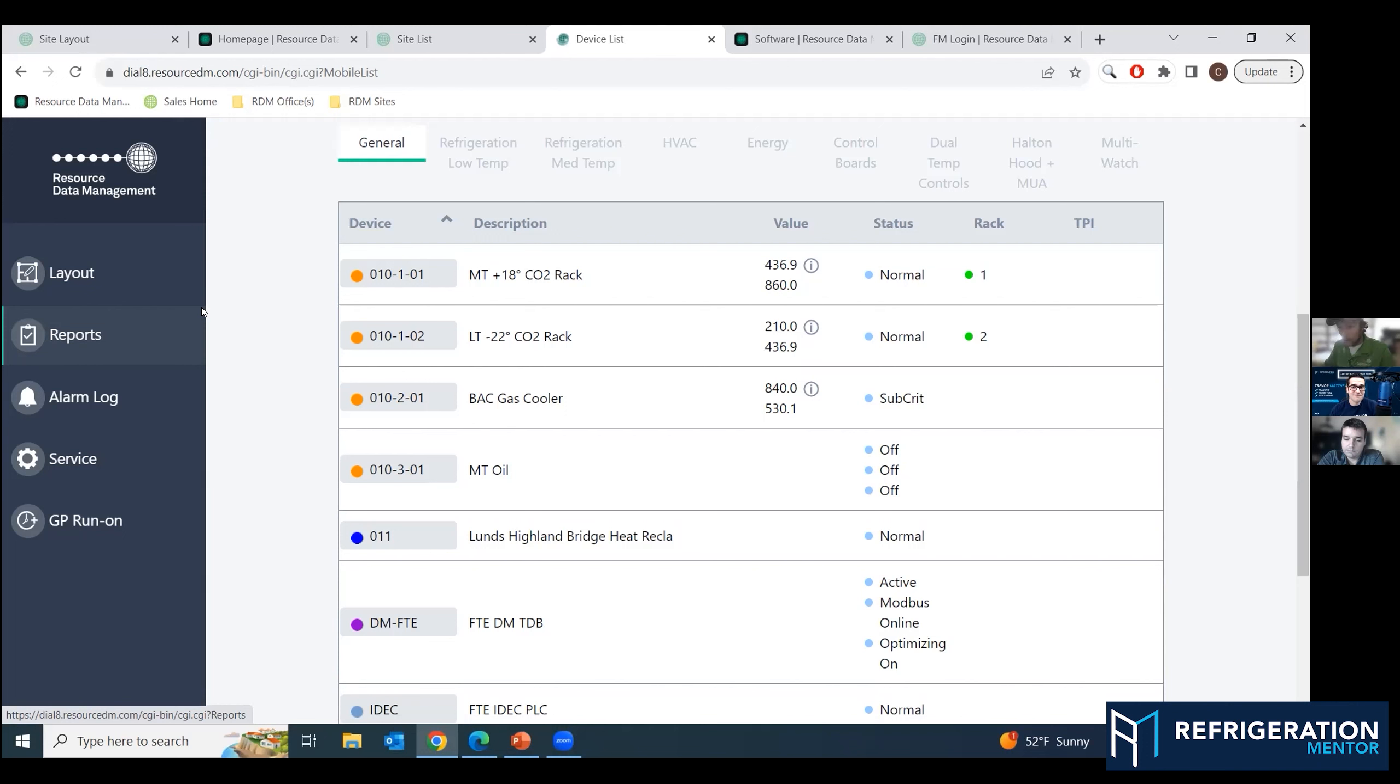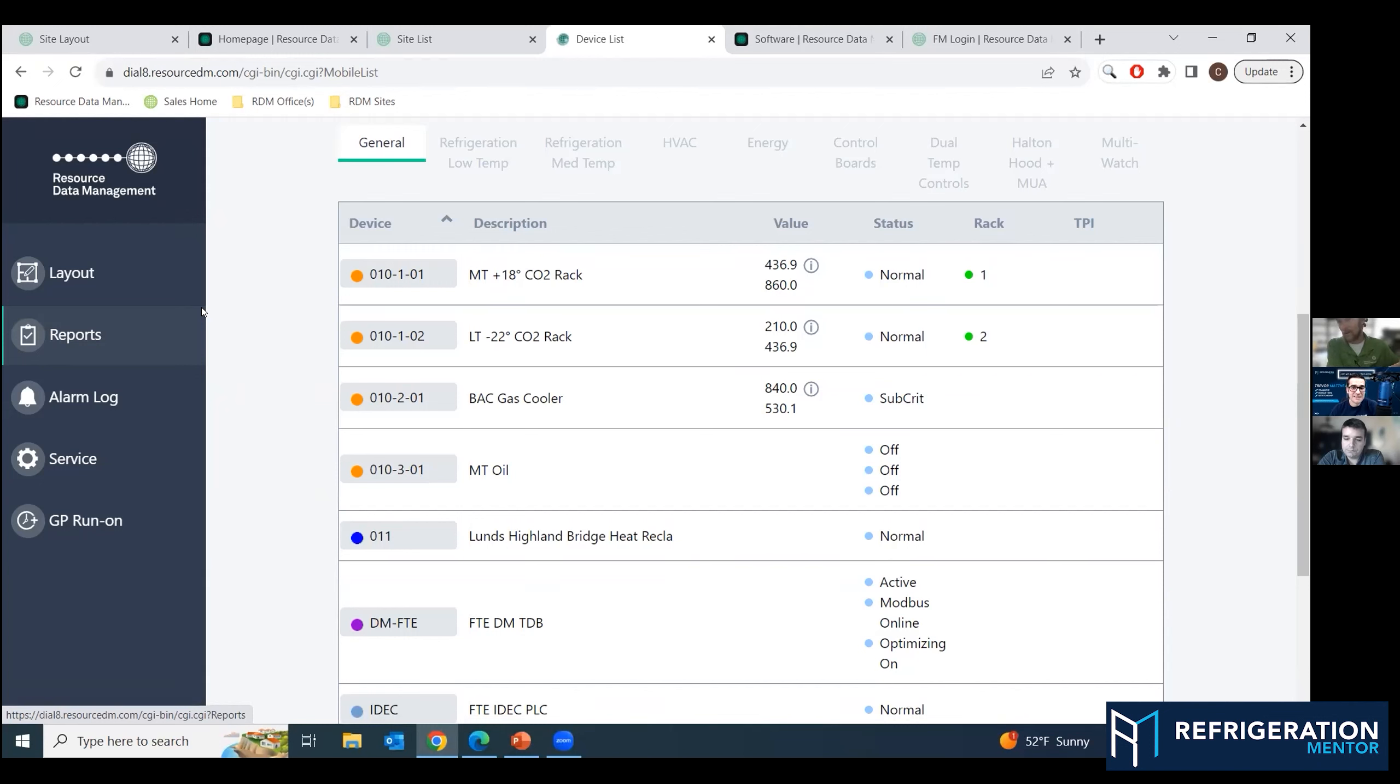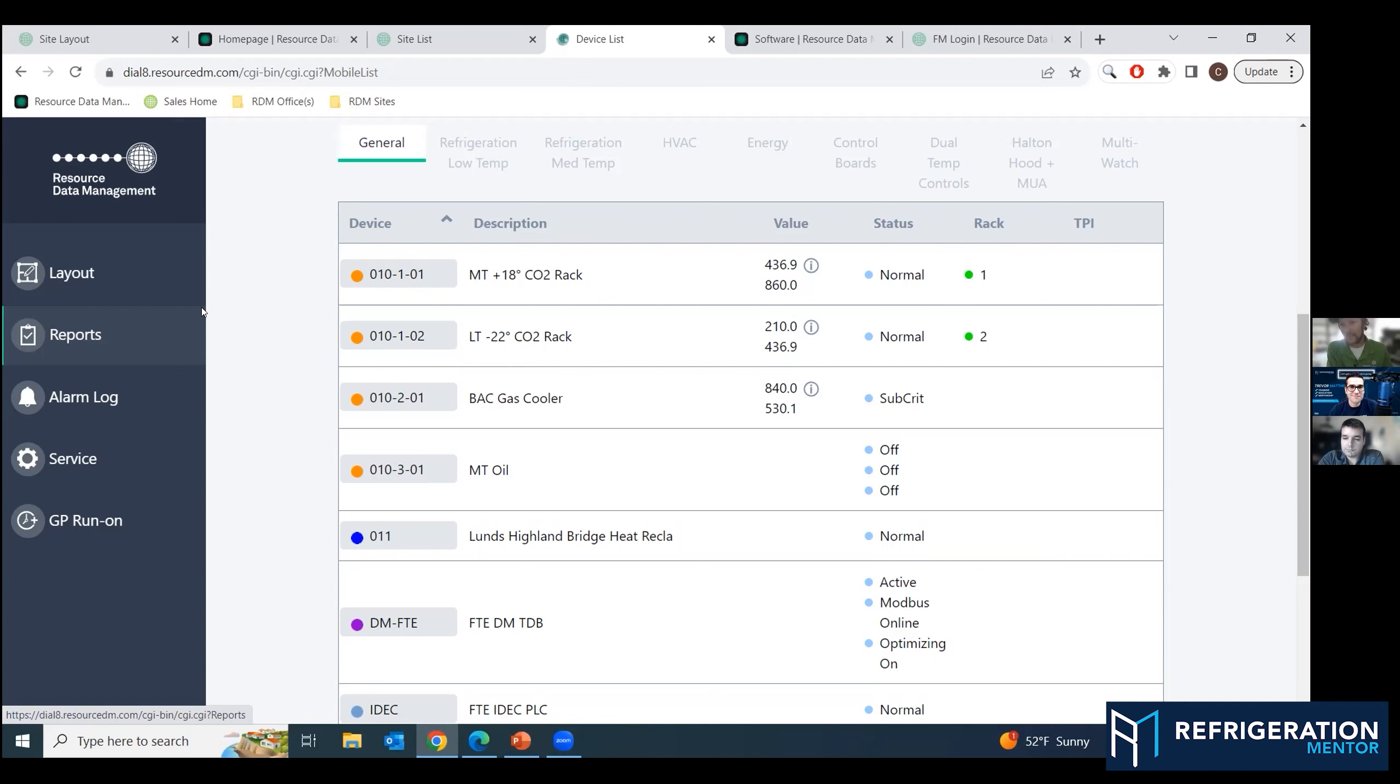Well, you got doors open and closing, you got drafts coming in and out, and you've got all this humidity over here. And then all of a sudden in the back of the store, you don't have all that humidity and you've got the same set points. And techs always wonder why, well, my case is, it's going through defrost, but it's still freezing up. Well, yeah, you kind of got to look at these certain things. And there is settings in the controller that can cause that 100%.